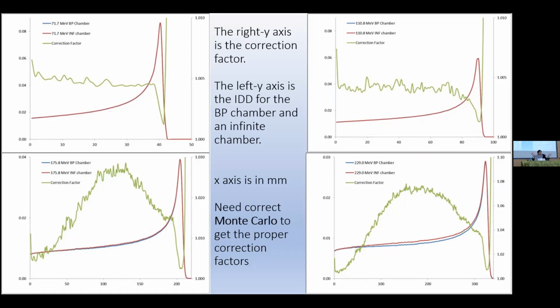Well, particularly that wide scatter, if your detector is not big enough, you're going to miss all these protons coming out. And if you're trying to do an absolute measurement, like say how many particles am I actually delivering here that's going into the patient, and how many am I delivering as a function of depth, you need to account for all those.